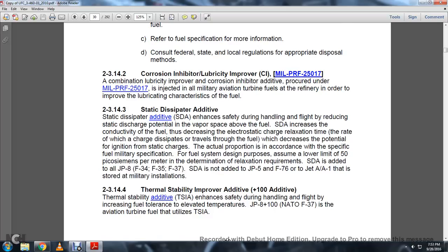2-3.14.3 Static dissipator additive. Static dissipator additives (SDA) enhance safety during the handling of the fuel by reducing static discharge potential in the vapor space above the fuel. The static dissipator additive increases the conductivity of the fuel and decreases the electrostatic charge relaxation time. The rate of charge dissipation or travel through the fuel, which decreases the potential for ignition from the static charge. The actual proportion is in accordance with the specific fuel military specification. For fuel system design purposes, assume the lower limit of 50 picosiemens per meter and determine relaxation requirements.